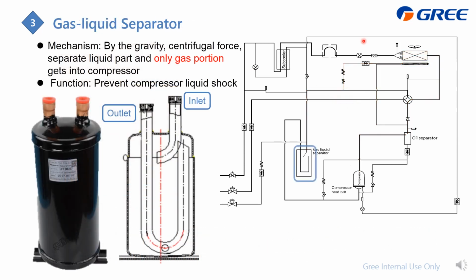Gas liquid separator located here. Here is the appearance. You have two parts. From this sectional view, you can find that here is the inlet and here is the outlet. The function of this one is that by gravity or centrifugal force it will separate the liquid part, which will accumulate here, and only the gas will flow up and from this tube get in it, and from here get outside, into the compressor.